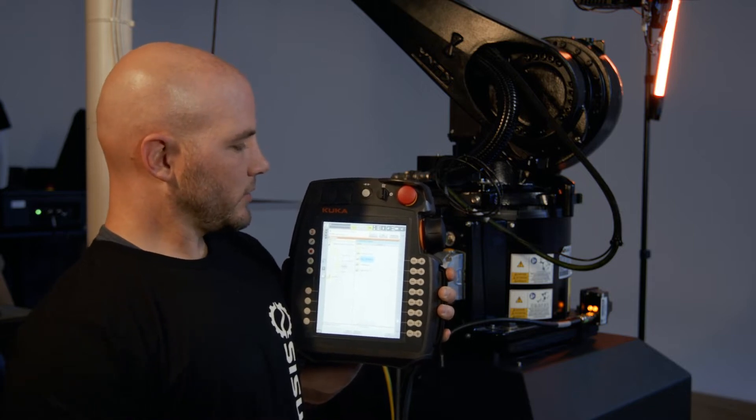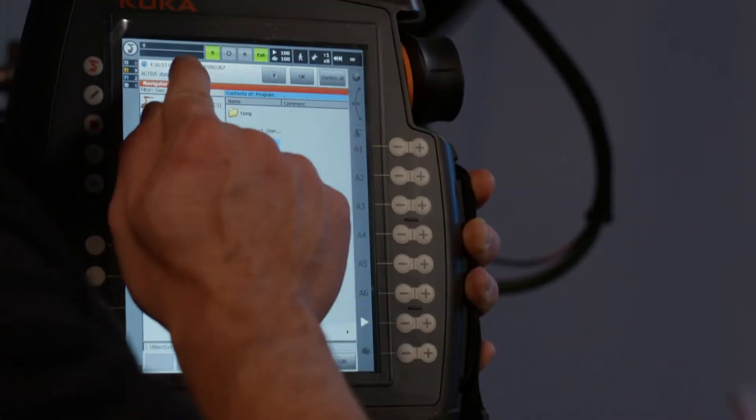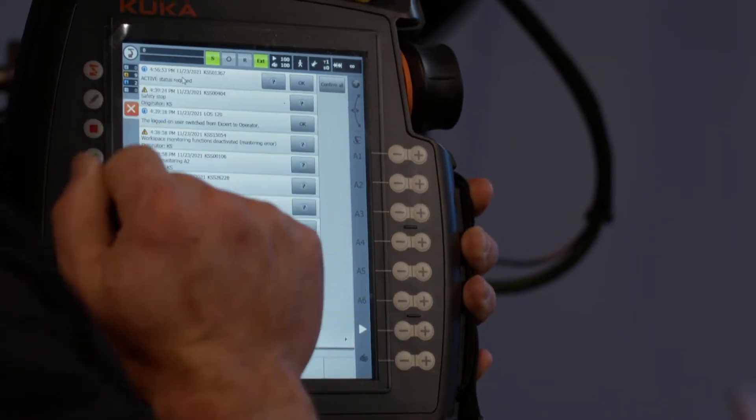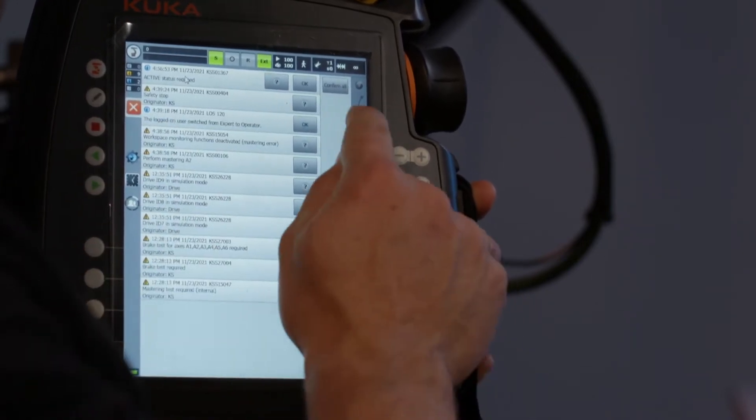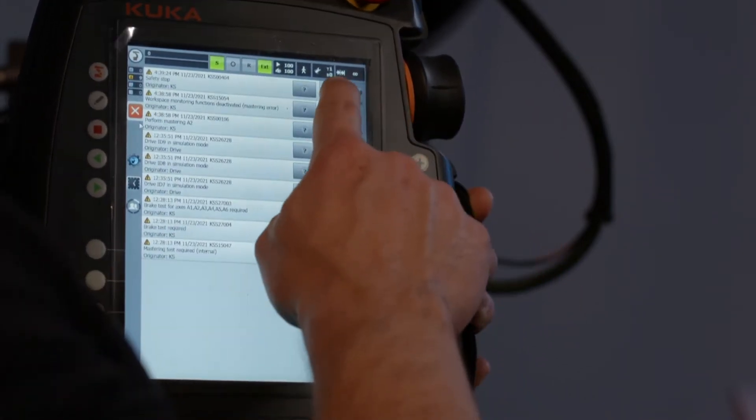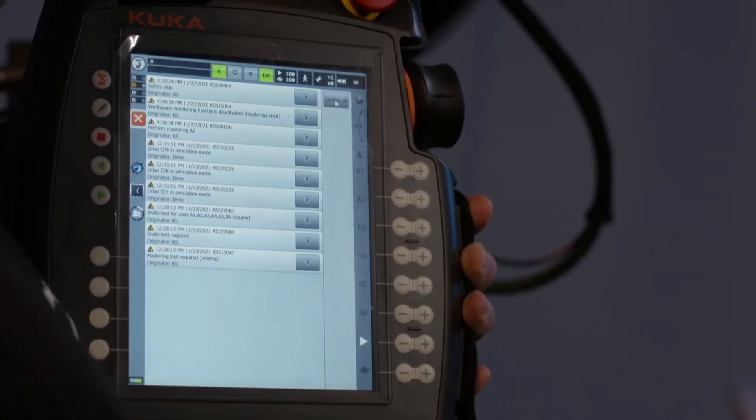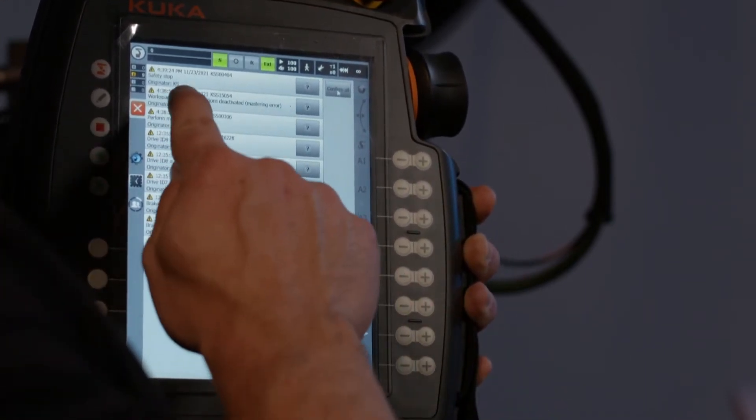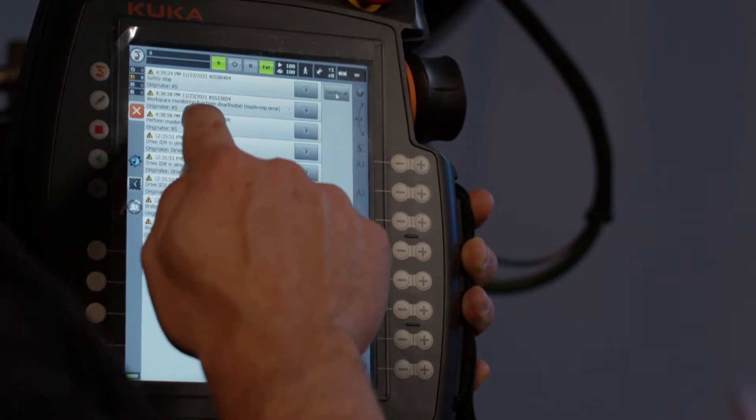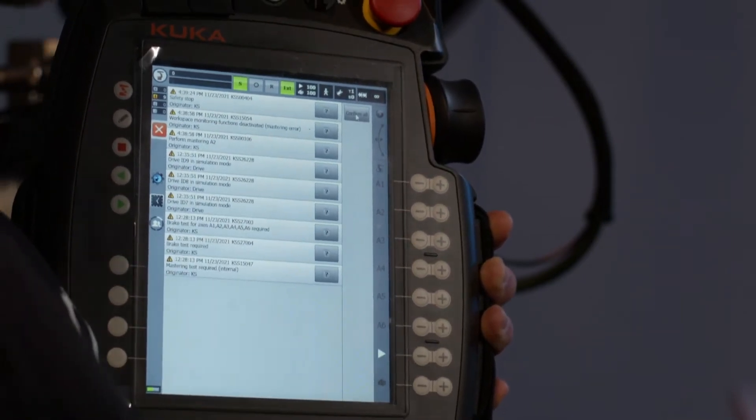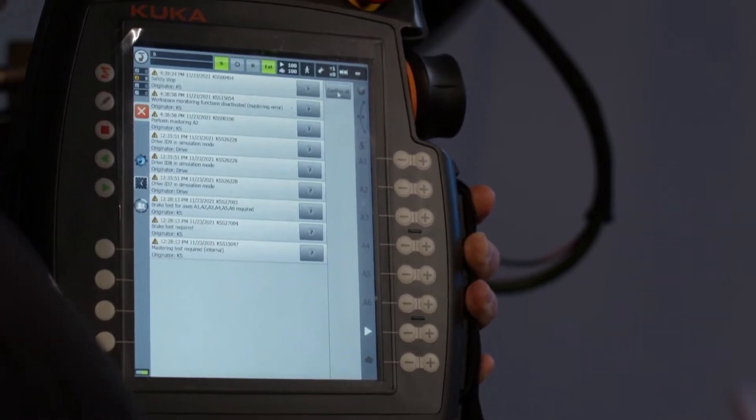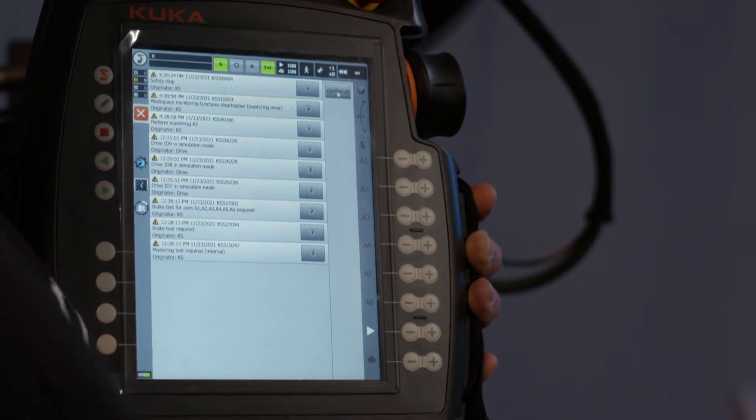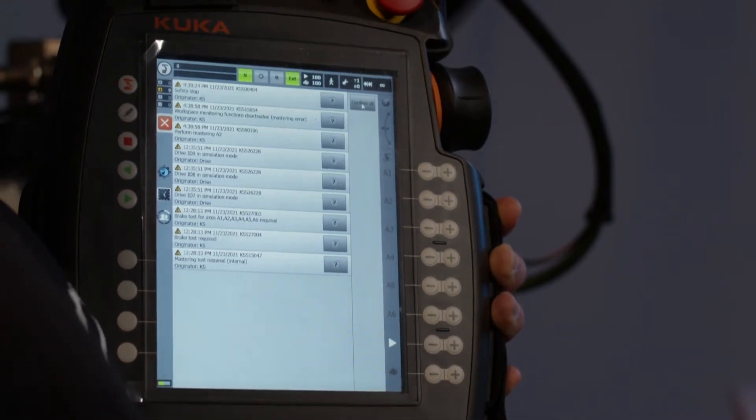What we're going to do is just click right here on the errors and messages. Say confirm all, that'll get rid of some of your messages. And then you'll see one that says perform mastering A2 or A3 or whatever that is. If you do see that, that means that you need to remaster that axis.